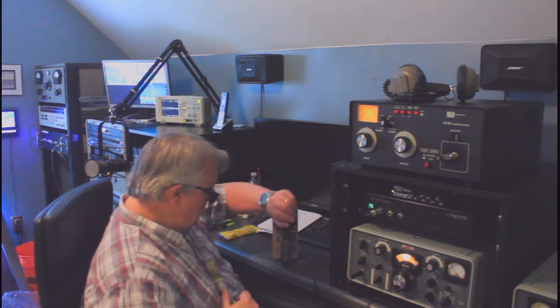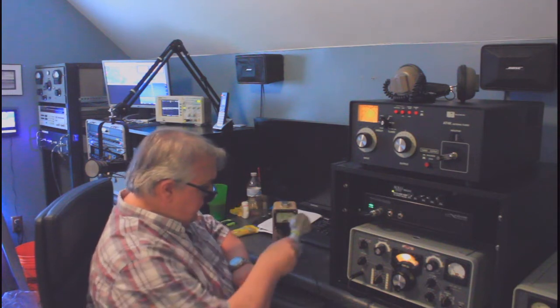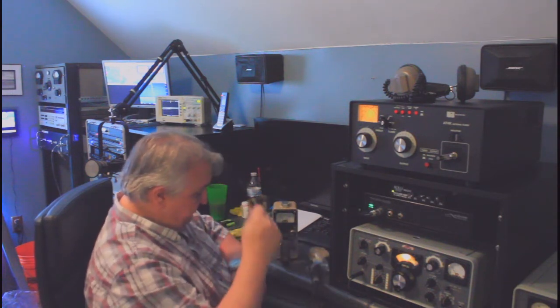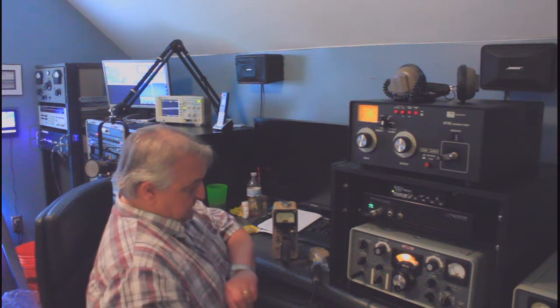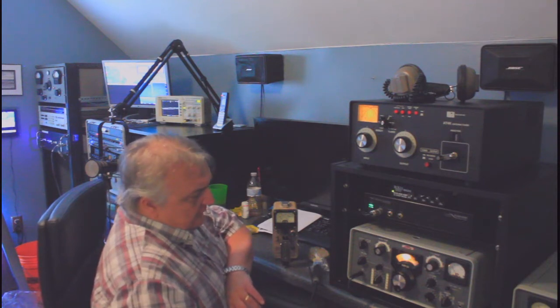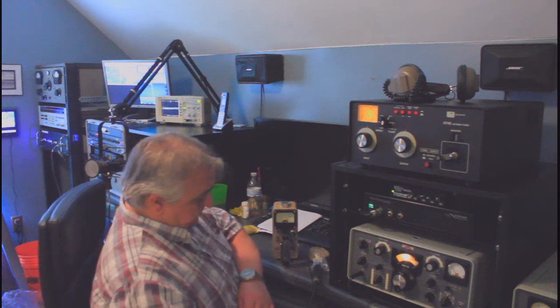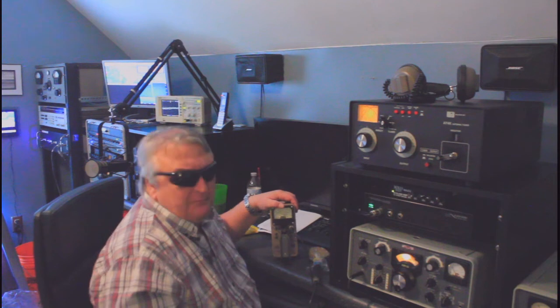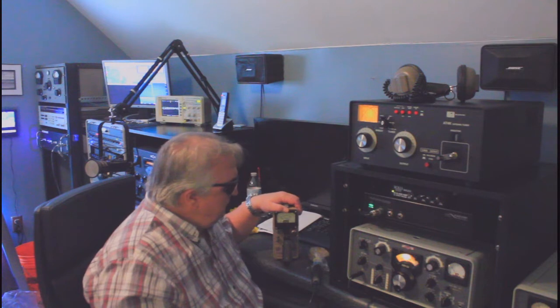Now, looking at my watch, let's put the watch against my body. Put it flat against the body so that the Geiger-Muller tube is parallel to my plane of emission here. That's a nice little phrase, plane of emission. And it's coming up 500 microsieverts roughly. So this watch, which is supposed to be calibrated, is very, very close to what we're getting on the Ludlum 12 with the Ludlum 44-9 pancake probe.